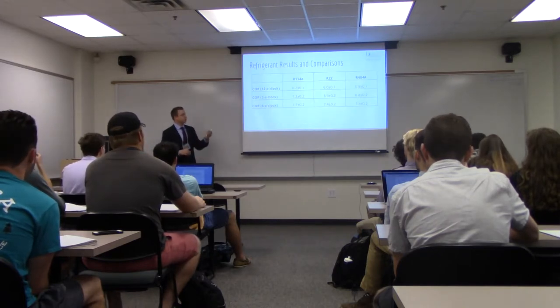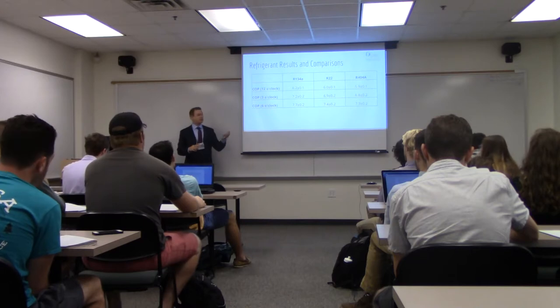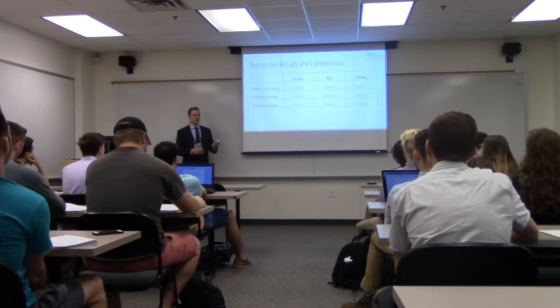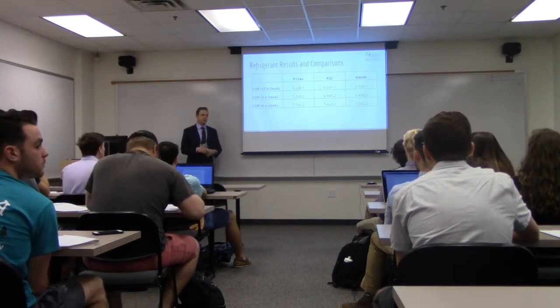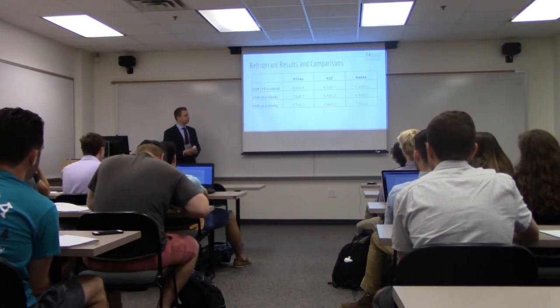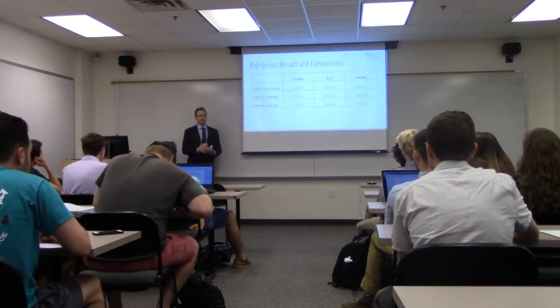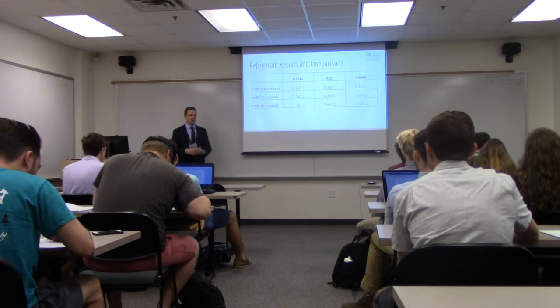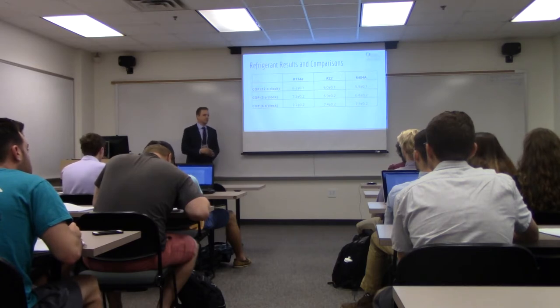These are all the results from testing R134A, R22, and R404A. R134A has the highest COP, which makes sense because the system is meant to run on R134A and the pressures were ideal for it. R22 usually runs at higher pressures, so if you were able to change the system pressure, the COP might have been higher. From 12 o'clock to 3 o'clock there is a large jump in COP, and then a smaller one from 3 o'clock to 6 o'clock. The COP follows a logarithmic curve, getting closer and closer to maximum, so no matter how high you turn the fan it will eventually reach its maximum. However, 6 o'clock is the highest fan speed available, so we couldn't test any higher.